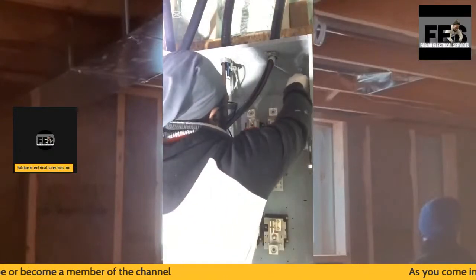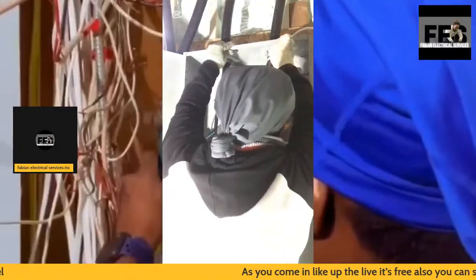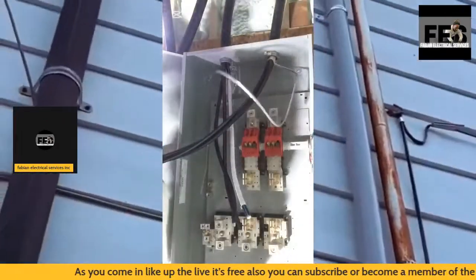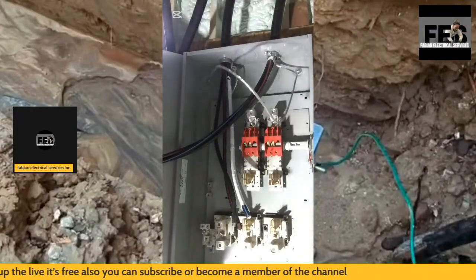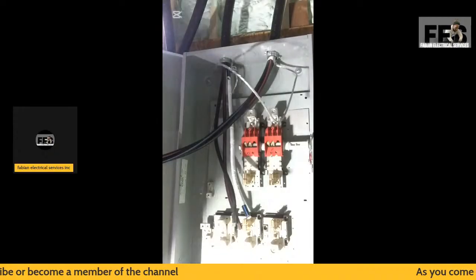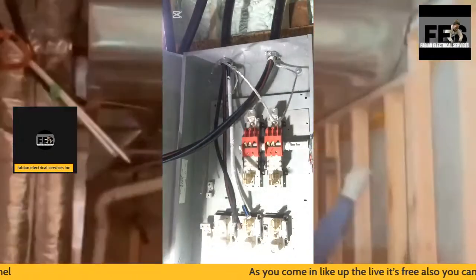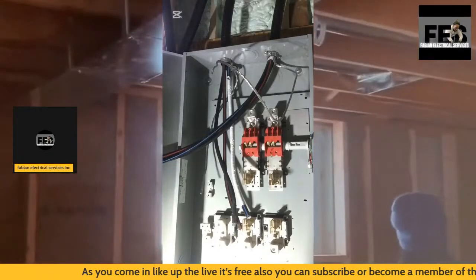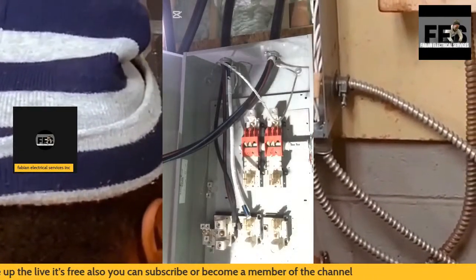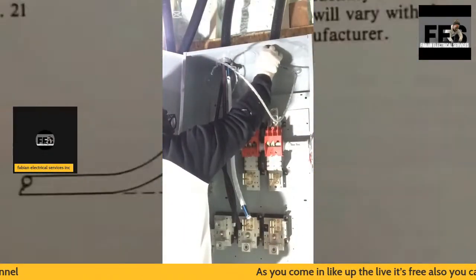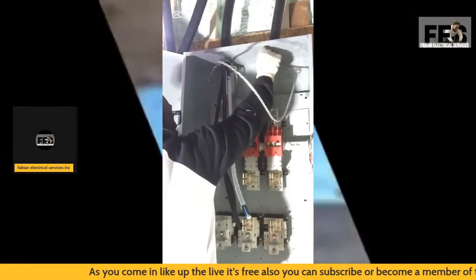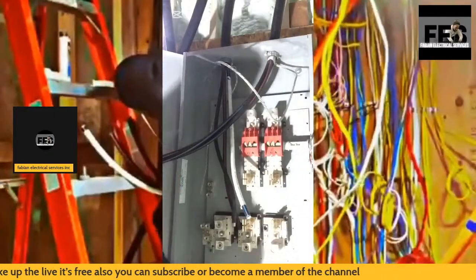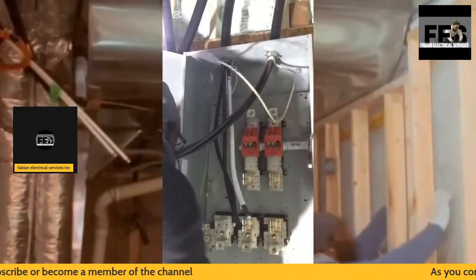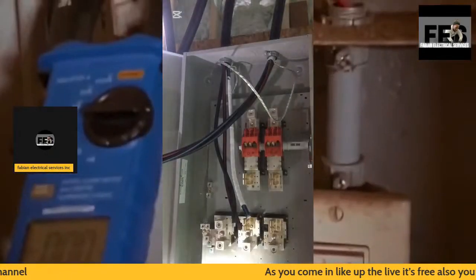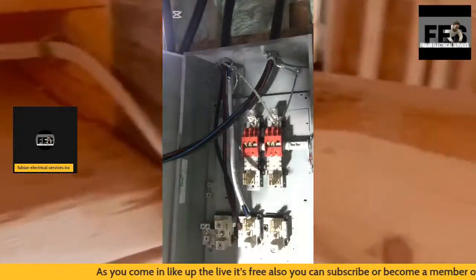Also, you're going to see I have my phasing tape on my cable. The reason is this cable does not come with an identified neutral, and in the code book it simply states that your incoming neutral has to be identified. There is an electrical code rule, code compliance, that states that for a particular size of cable we must identify up to. So this is what I am doing here, identifying my conductors with the white tape that is being used. It's always best to have your line and loads coming in be separated. Never have them touching each other. It is a code compliance rule that states that your main feed coming in is not supposed to come in contact with your actual load side that's going out. So for this reason, you're going to see the installation.